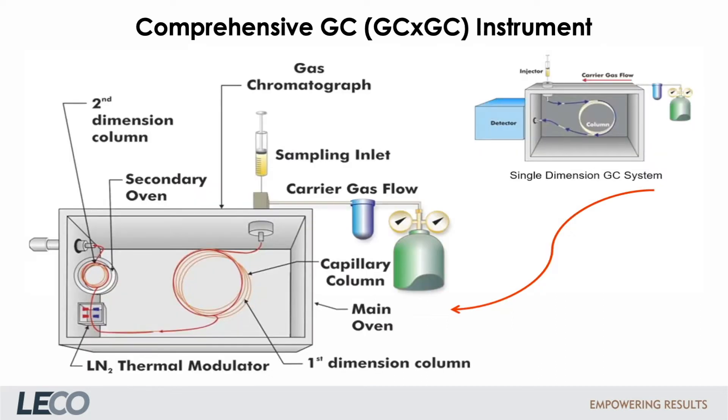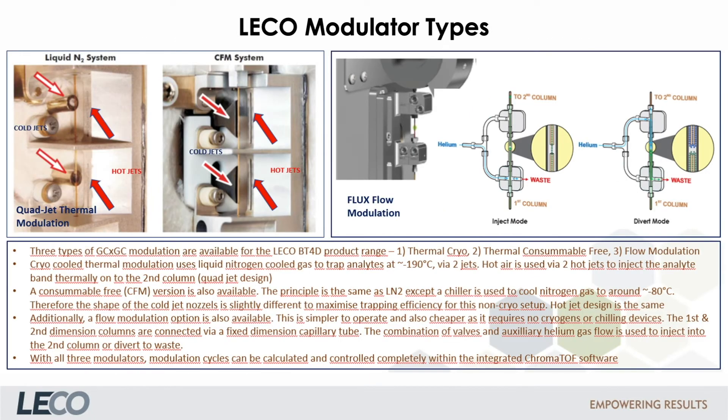For GC×GC operation, we have to modify the standard GC and add two additional components: a modulator and a separate oven for the second column, allowing for controlled temperature offsets to be applied. The functionality of the modulator has already been described. The trapping and releasing effects during modulation generate very small peaks in the second dimension and therefore result in increased sensitivity. Three types of GC×GC modulation are available for LECO systems: thermal cryo, thermal consumable free, and flow modulation.